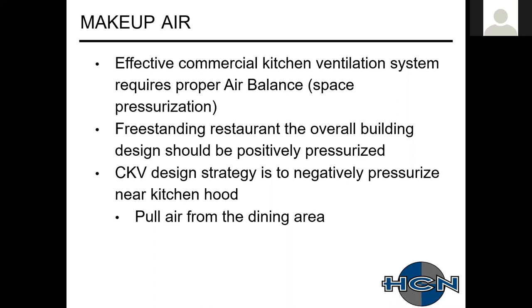the ceiling. So to complicate things a little bit further, this commercial kitchen system is just a subset of the overall building HVAC system. So if those systems are fighting each other and not working properly, you could have some ill effects as well. But the major thing here is there's no real magic in a commercial system. Your exhaust hood sucks air out. You're required to bring that air back in. It's pretty simple physics.